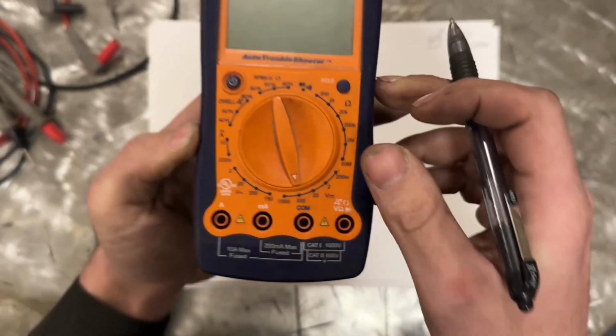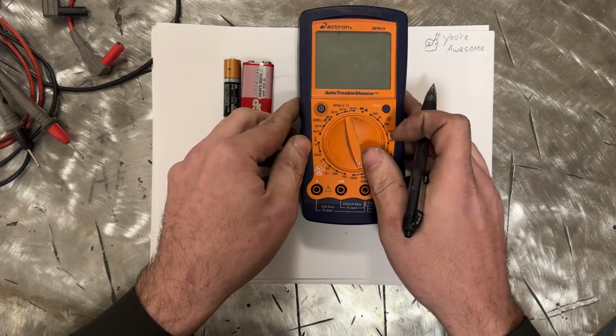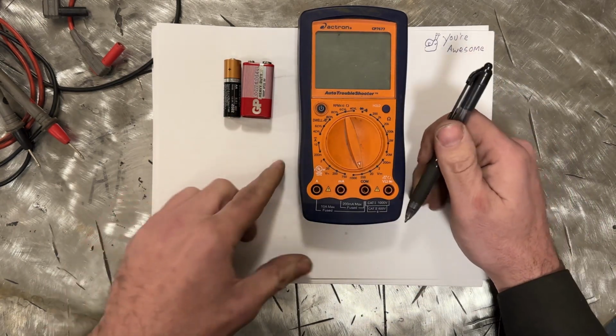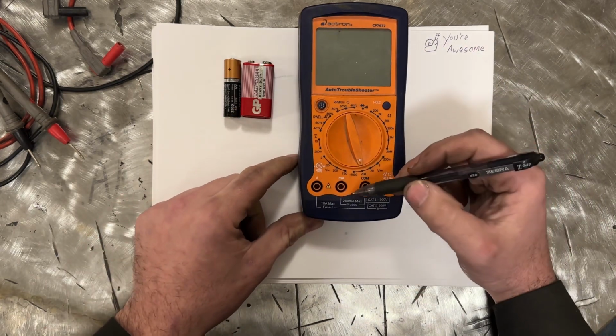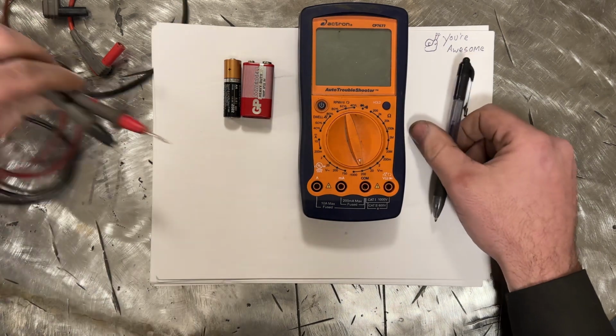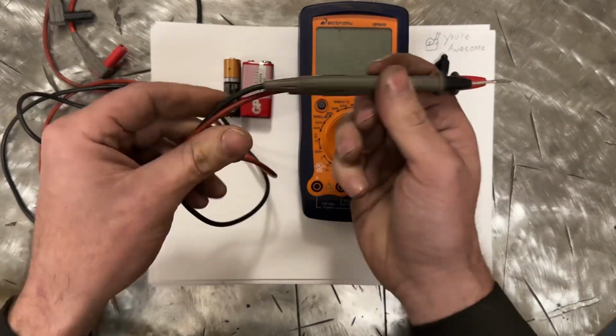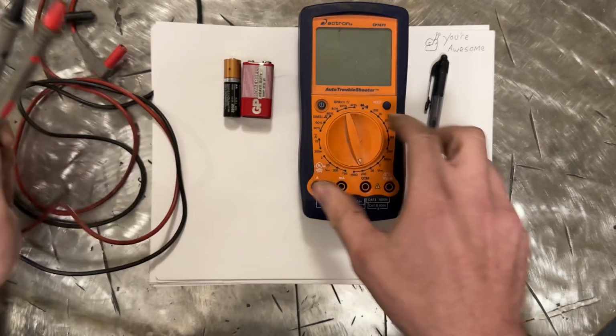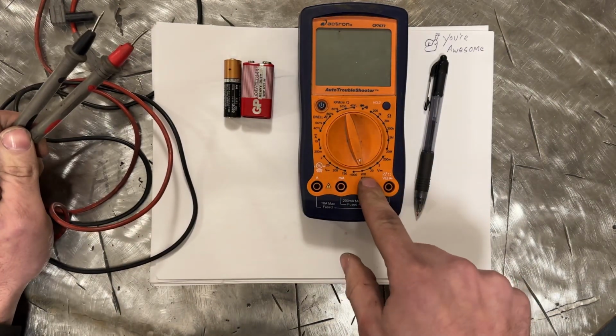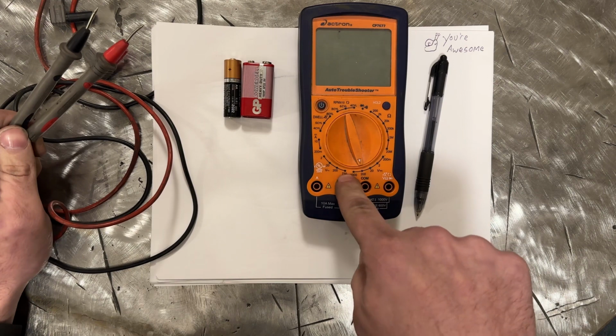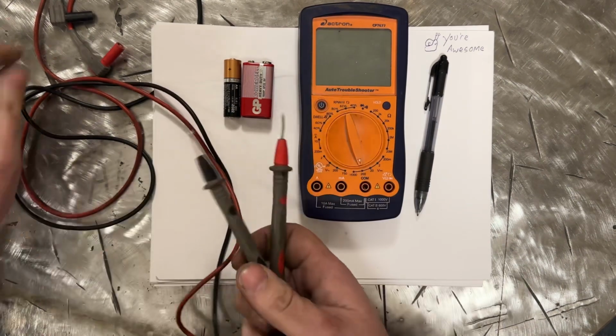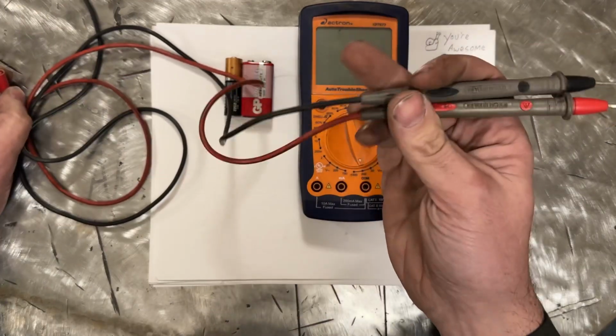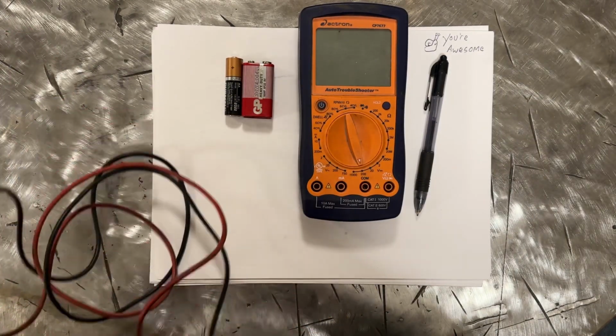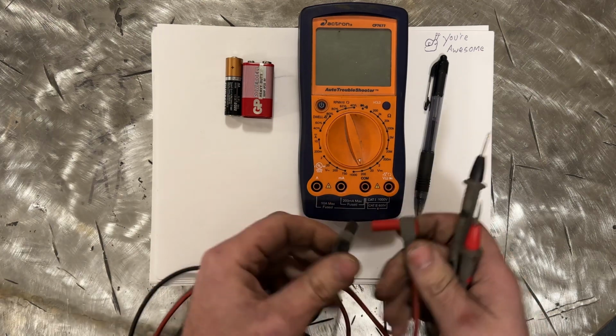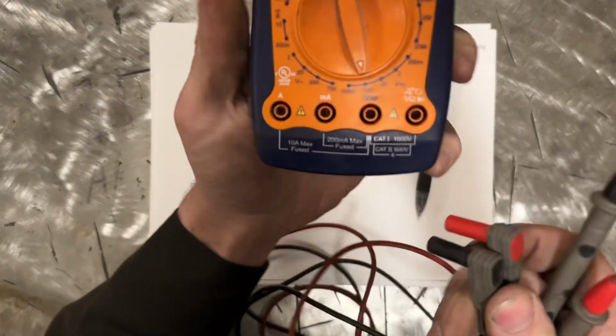You always want to make sure that whatever you're testing, say if you're testing 500 volts AC, your meter is rated for it and that you have proper test leads that don't have cracks in the wire. If you use this meter, which apparently is rated for 1000 DC and 750 AC, and you hook this to 1500, you're likely to shock yourself right through these cables because they will become conductive and they won't be able to hold the voltage back.